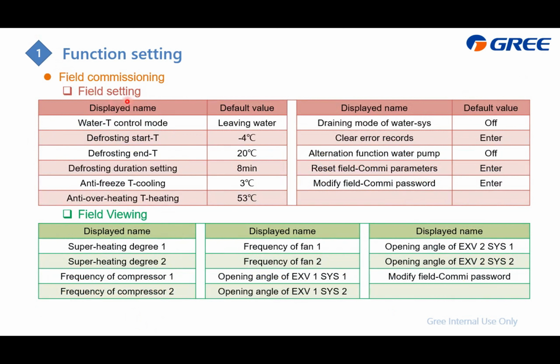You can find all the parameters and also functions for the commissioning, where you tell the system which function you would like. For example, the most important is the control target. The default setting is the water out, which is the leaving water temperature. You can also change this to the water in temperature. And for the defrosting, the detail, you can also change it. And of course, for this function you should have enough experience.